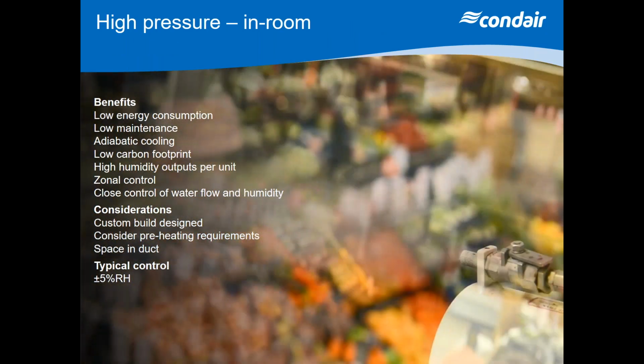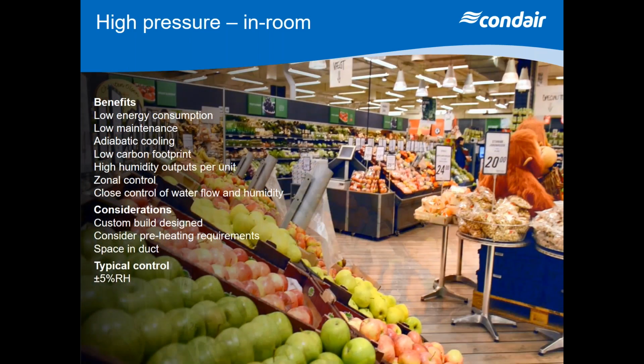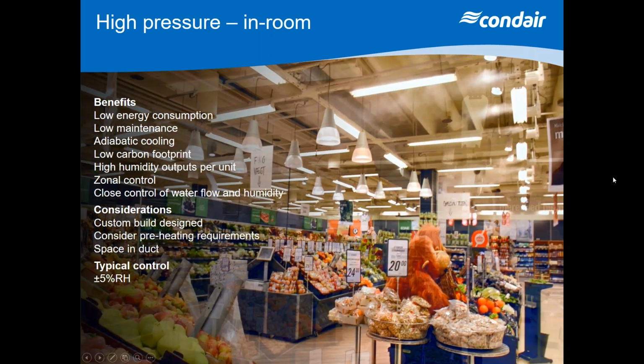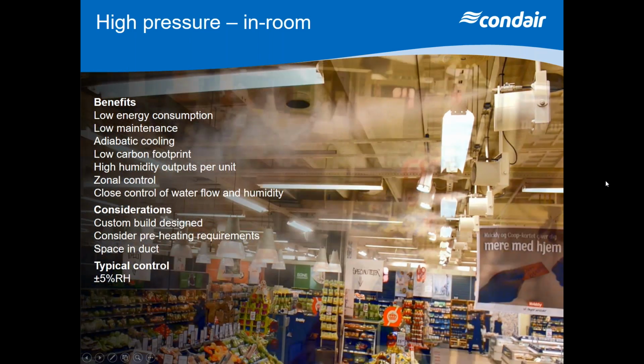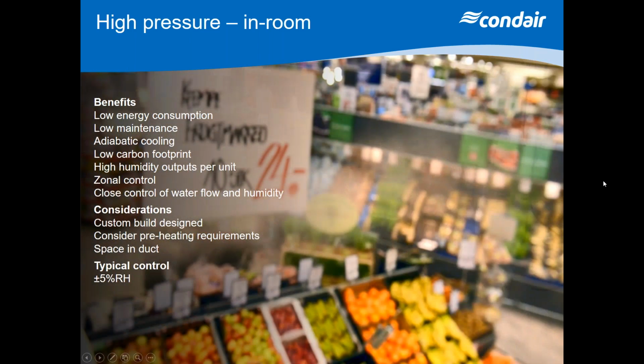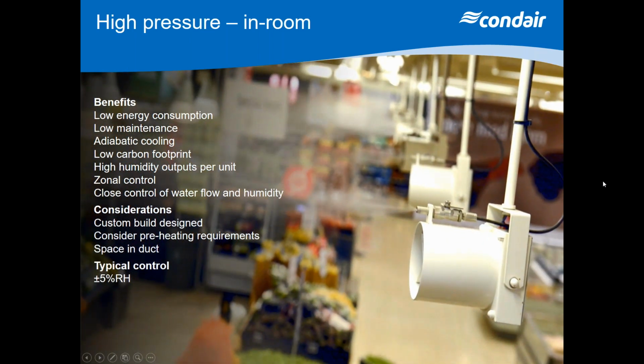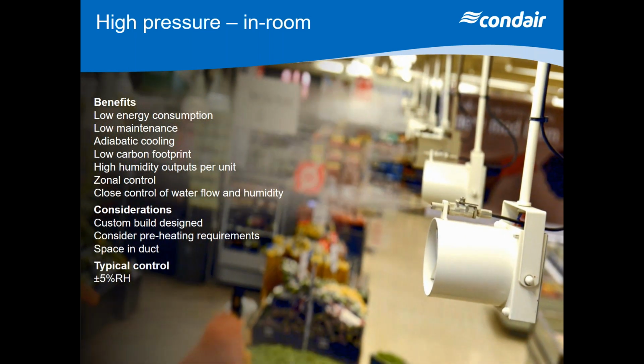And here you can see a high pressure system in the supermarket. With a high pressure system, we would take RO water and tube it to a number of heads, and we'd almost have a ring main going around, and we would tap into that ring main and spray out into spaces. Now, the way that we get zonal control is by having local sensors or stats and local valves. So we can allow water to go to a number of these spray heads in the system. So I can get zonal control, great if you've got an area where you've got two climatic conditions, or indeed you've got areas that are subject to solar gain that could alter your controllability.